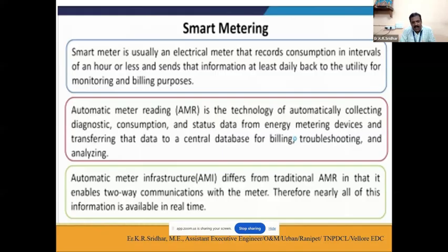The next one is automatic meter infrastructure (AMI), which differs from traditional AMR meters in that it enables two-way communication. AMR only collects data from devices on consumption and grid status and sends it to a central database, whereas AMI has two-way communication with the meter. Therefore, nearly all information is available in real time, since control can be given from utility to grid, or data transferred from grid to utility. This two-way communication facility makes the grid smarter.